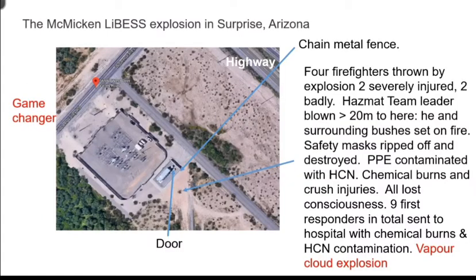Now, this is what changed the whole game. This was an explosion in Surprise, Arizona. The local fire service did not know they had one of these battery energy storage systems on site. The smoke alarm triggered because, as per usual at that time, they were using a gaseous suppressant, which does not stop thermal propagation - it kills the fire, but the cells continued in thermal runaway. In fact, there was no fire before or after the explosion.